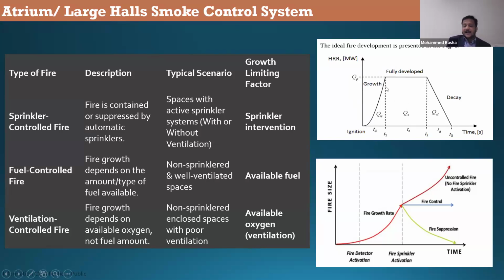If the same fire is happening in an enclosure where you have sprinklers, the development will not be the same. What happens? Look at this bottom figure here. After the growth time, the sprinkler starts to control the fire, because the sprinkler will activate probably at 200 seconds, 300 seconds, sometimes 80 seconds, 60 seconds, depending on the growth rate of the fire. Once the sprinkler starts to control the fire, the steady state will not continue. I mean, an uncontrolled fire should go higher, then go horizontally to a steady state, then start to decay.